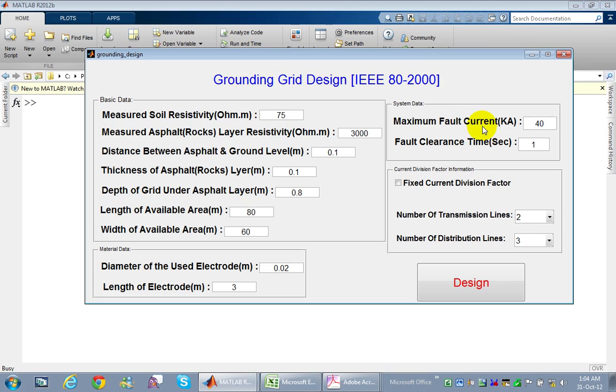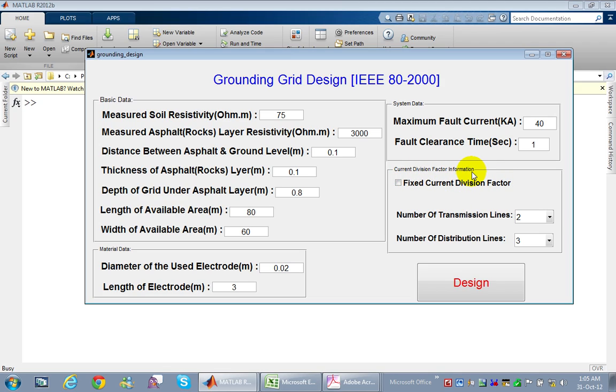Under system data, we enter the maximum fault current. For a 132 kV high voltage substation, the maximum fault current is 40 kiloamperes for one second, though this depends on the client and country specifications.